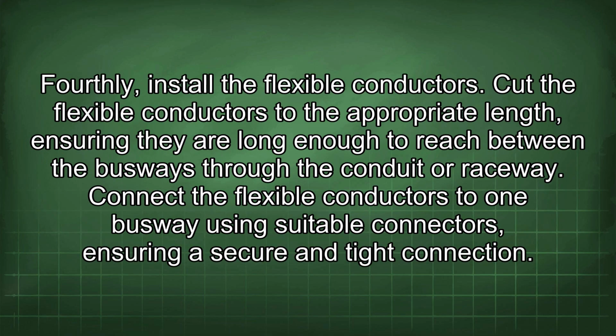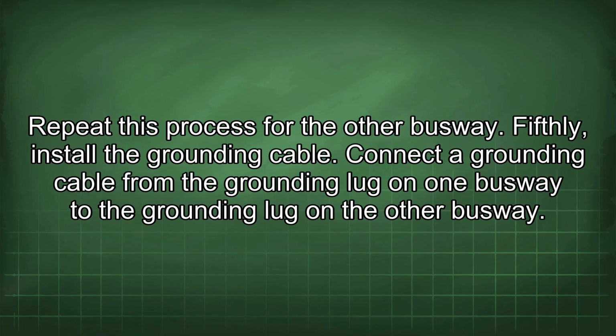Fourthly, install the flexible conductors. Cut the flexible conductors to the appropriate length, ensuring they are long enough to reach between the busways through the conduit or raceway. Connect the flexible conductors to one busway using suitable connectors, ensuring a secure and tight connection. Repeat this process for the other busway.